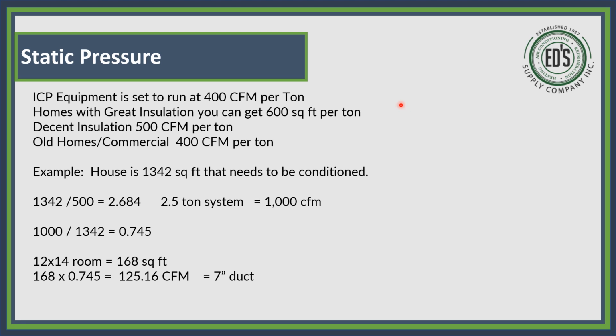Example, let's say a house is 1,342 square feet and it needs to be conditioned. Well, if I take 1,342 and I divide it by 500, because I'm saying it has decent insulation, I get 2.68. So we're going to call that a 2.5 ton system, 1,000 CFMs. So I take my 1,000 CFMs and I divide it by 1,342, that's what size the house was, and I get a 0.74. That is how many CFMs that house needs per square foot to heat and cool that house properly.